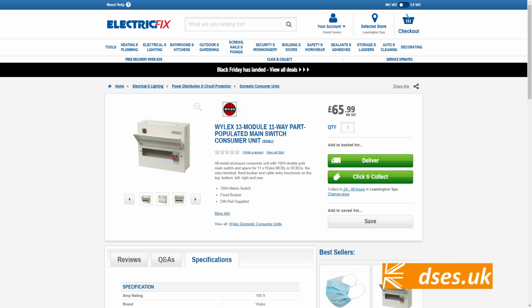And cost is a second reason. Why should I fork out to replace my perfectly sound enclosure with a steel one? I would if it were a customer site, of course, because I do my best to comply with BS 7671. But this is my property, fully inspected, tested, maintained to a good order. It's not in an escape route, and it is about to be outfitted with the very latest in protective devices. Sure, plastic doesn't contain a fire as well as steel might, but if it's properly installed with the correct rated devices, all torqued up, and those devices are type compatible with the enclosure, as Wylex have confirmed to me in writing that these are, then why should it be at risk of spontaneous combustion? Do I need to spunk out tens of quids on a metal box?